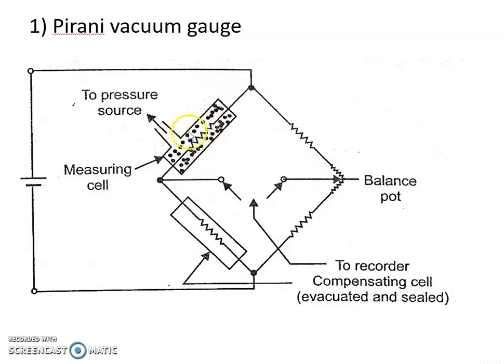When there is a change in pressure, the temperature of this filament changes, and because of the change in temperature, the resistance of this filament changes. A compensating cell is also employed to minimize variation caused by ambient temperature changes.